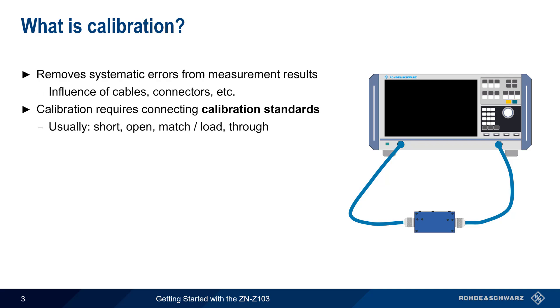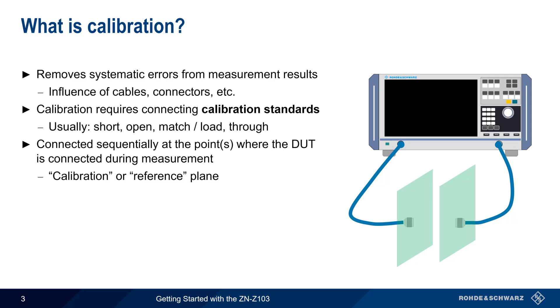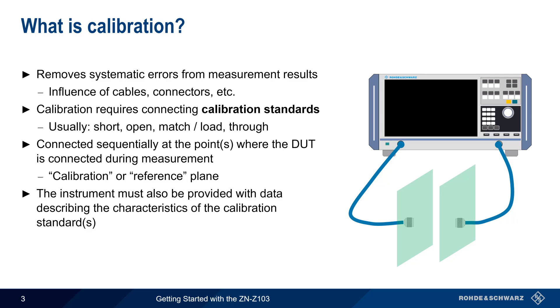These are usually a short, an open, a match or load, and a through. These are connected sequentially at the point or points where the device under test will be connected during measurement, and this is often referred to as the calibration or reference plane. In addition, the analyzer must have information regarding the characteristics or the frequency-dependent behavior of the calibration standards being used.